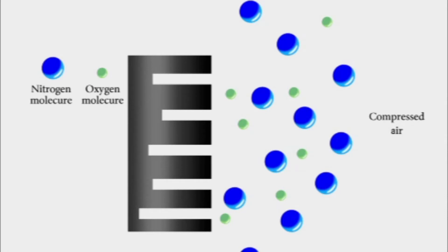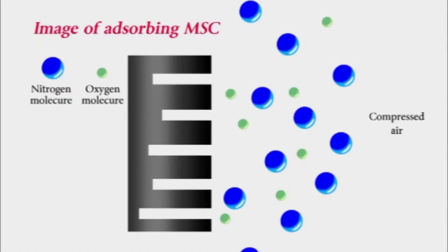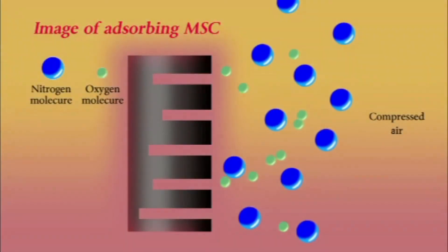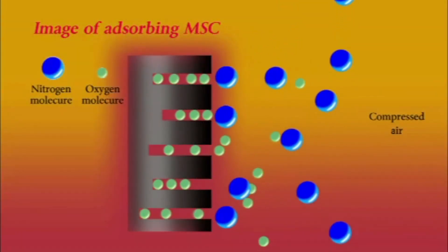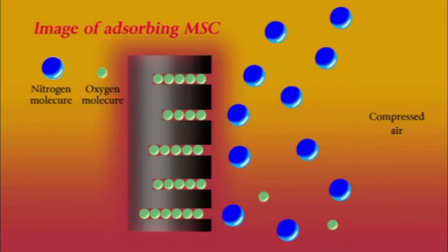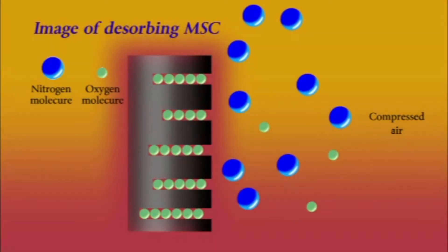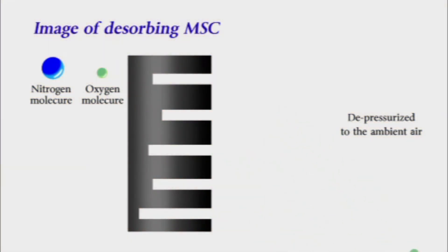Here we can see how the adsorbing and desorbing processes are carried out on this adsorbent. Innumerable microscopic holes exist on the surface of the adsorbent. The size of these holes is larger than that of an oxygen molecule, but smaller than that of a nitrogen molecule. When the compressed air is supplied to this adsorbent, only the smaller oxygen molecules are adsorbed. By pressurizing the adsorbent for a certain period, they are enriched and saturated with oxygen. By depressurizing these adsorbents to the ambient pressure, the oxygen molecules are completely removed, and they are ready for the next adsorbing process.